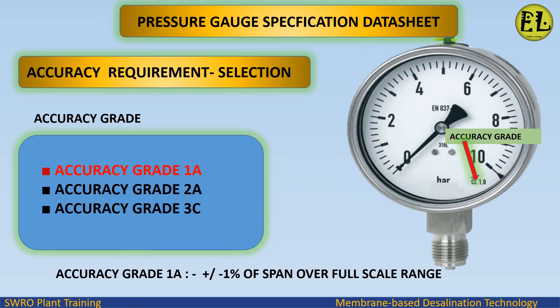Accuracy requirement selection. Accuracy grades available are 1A, 2A, and 3C. We select accuracy grade 1A, which is plus or minus 1% of span over the full scale range.